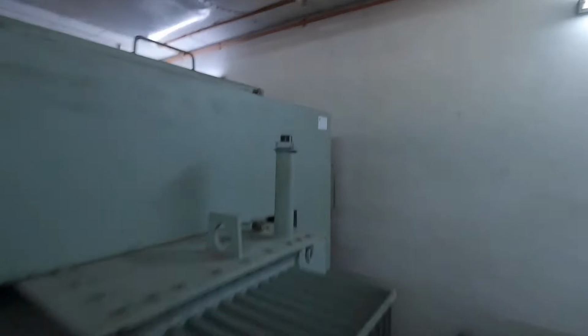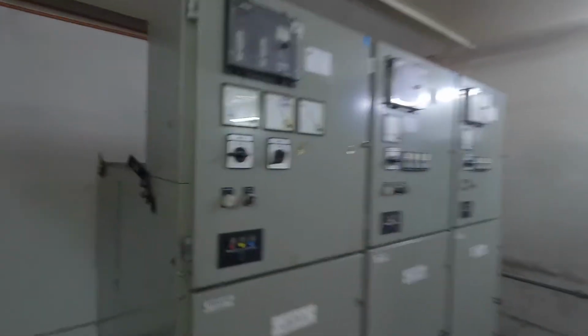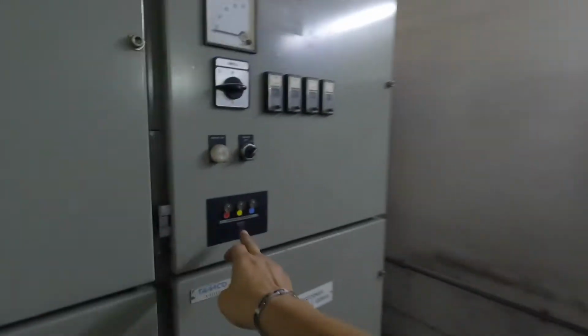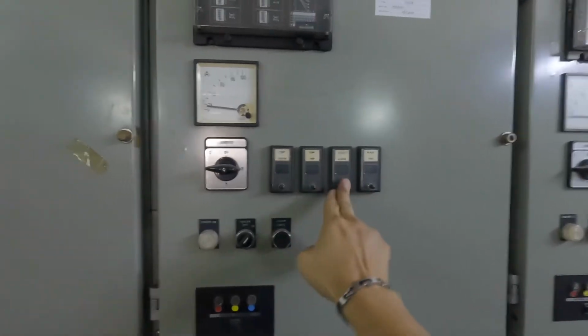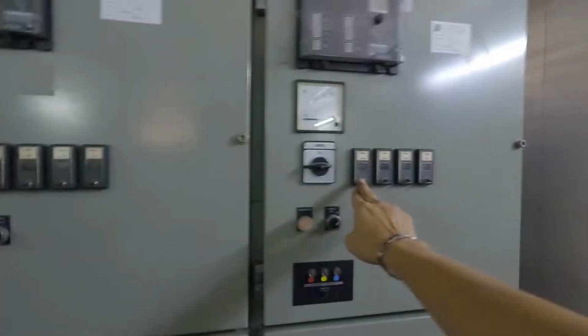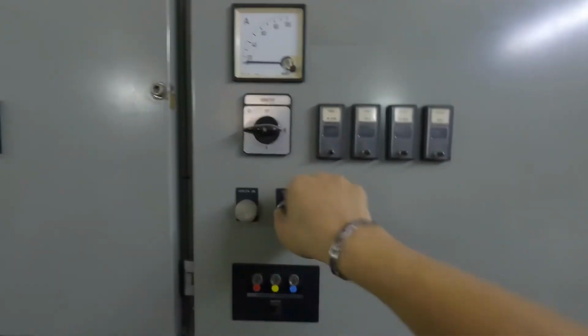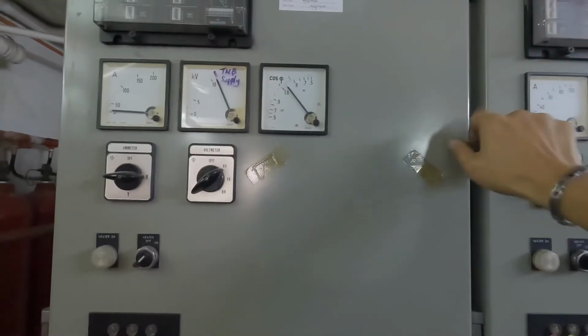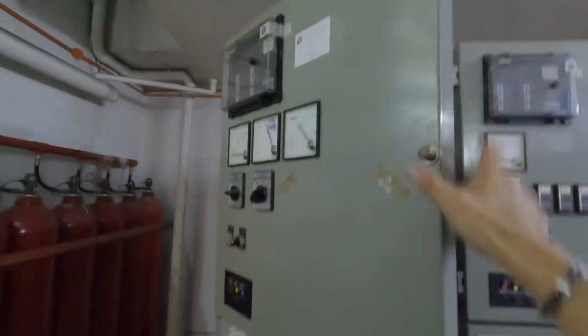Okay, oil level is quite high, no issue here. Oil level. Okay, oil available. Here as well, oil level available. No issue here. Okay, all the protection indicators, no jam. Okay. Okay, I'm going to check the heater and make sure the heater is in good condition by checking the amp of all the heater.